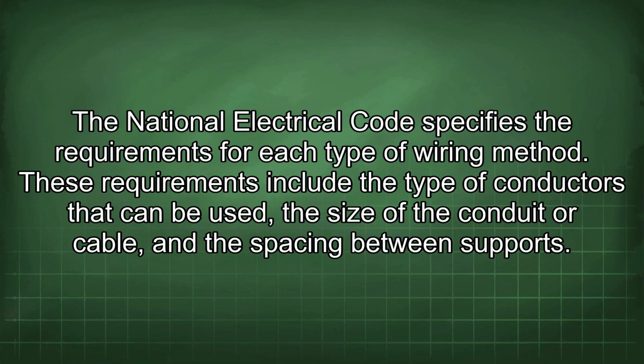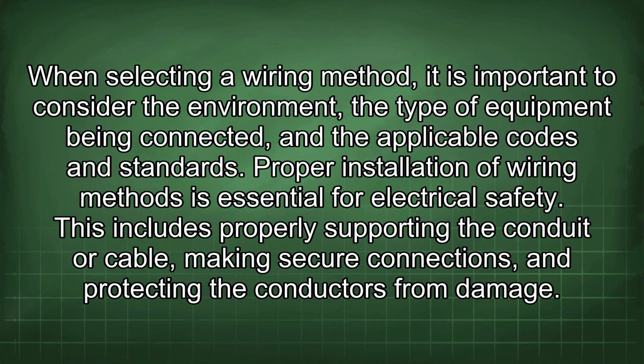The National Electrical Code specifies the requirements for each type of wiring method. These requirements include the type of conductors that can be used, the size of the conduit or cable, and the spacing between supports. When selecting a wiring method, it is important to consider the environment, the type of equipment being connected, and the applicable codes and standards.